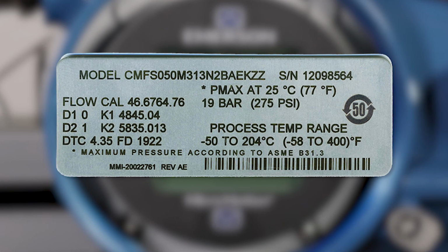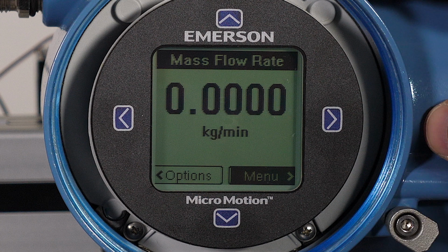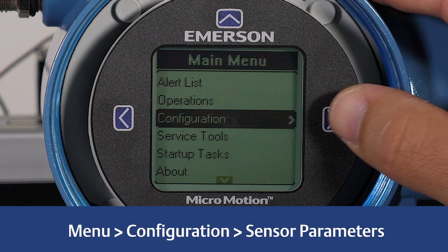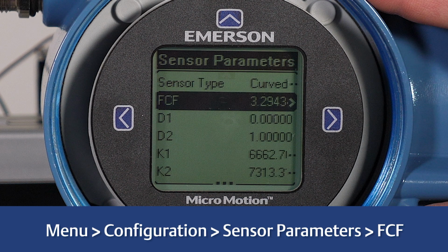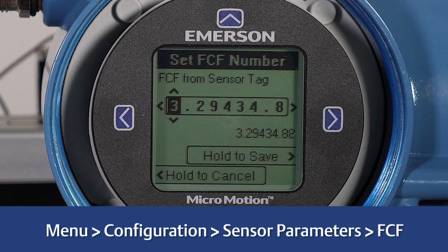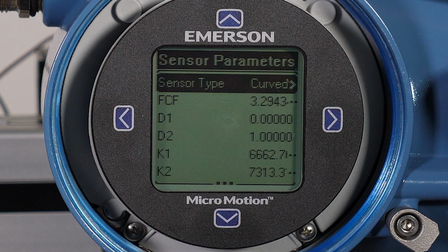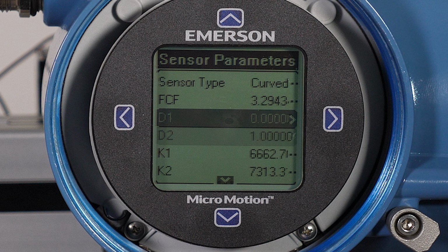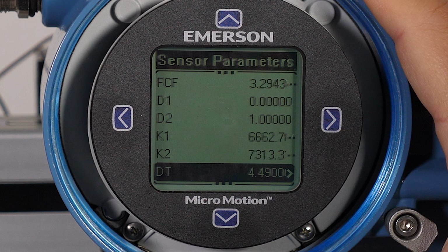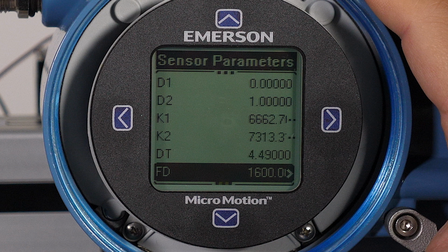First, record the following calibration and characterization parameters from the sensor tag or calibration sheet: K1, K2, D1, D2, FCF, DTC, or sometimes labeled as DT and FD. Second, using the display, select Menu, Configuration, Sensor Parameters. Third, set the flow calibration factor, also known as FCF or flow cal factor. Be sure to include all decimal points. Fourth, set the characterization parameters D1, D2, K1, K2, DT, and FD as necessary, and apply changes for each parameter that has been changed.